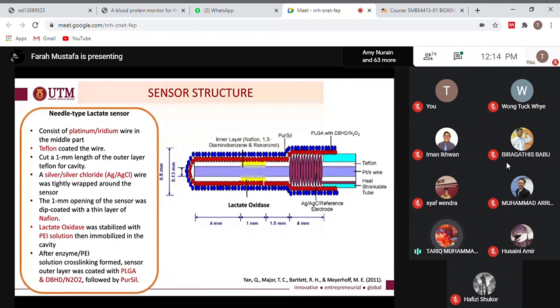And after that, they use a silver or silver chloride wire, and it is tightly wrapped around the sensor. And as I mentioned just now, the 1 millimeter cavity will be dip coated with a thin layer of Nafion. This thin layer of Nafion can be seen from the yellow image there at the upper region of the platinum and iridium wire. And after that only, they insert the lactate oxidase, which has been stabilized by PEI solution, or polyethylenimine, and it is immobilized in this cavity.